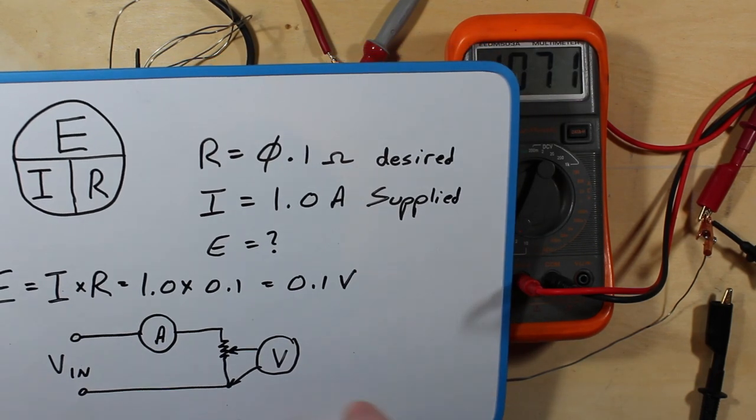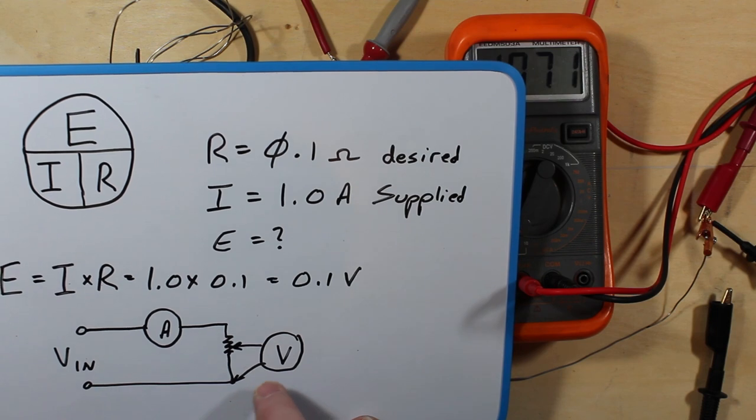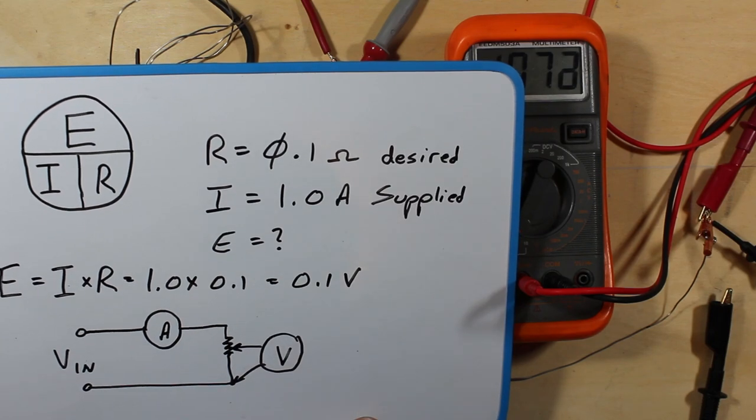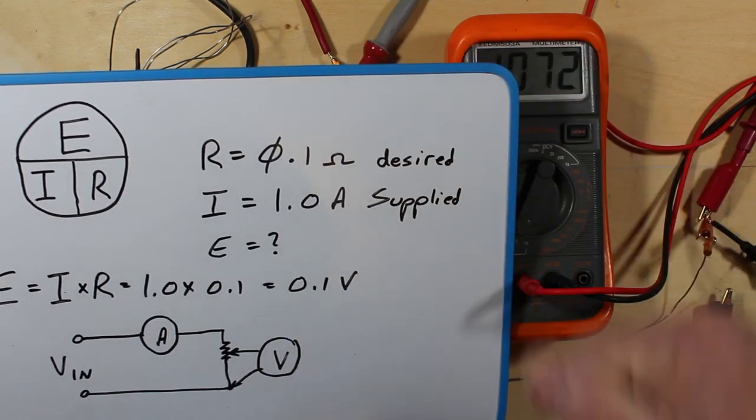So we're going to probe this wire with the multimeter, with the voltage meter. We know we've got 1 amp coming through here and we're going to be looking on here for 0.1 of a volt. And that will equate to 0.1 of an ohm.